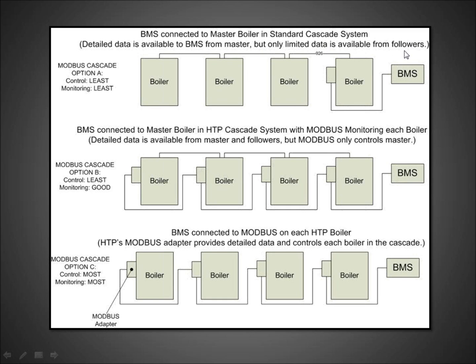So the master boiler is basically controlling through our boiler program what the followers are doing, and the building management system is monitoring what that's doing. And it's got limited availability of information on each connected follower boiler. So this, as far as our discussions yesterday, is probably the most limited in a cascade installation amount of information you can acquire for the bank of equipment tied to a building management system.